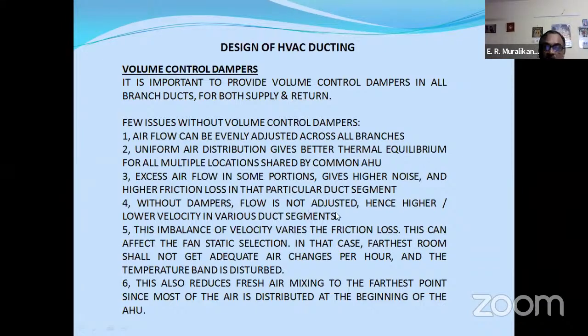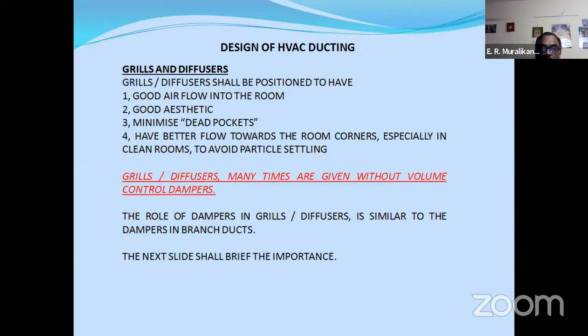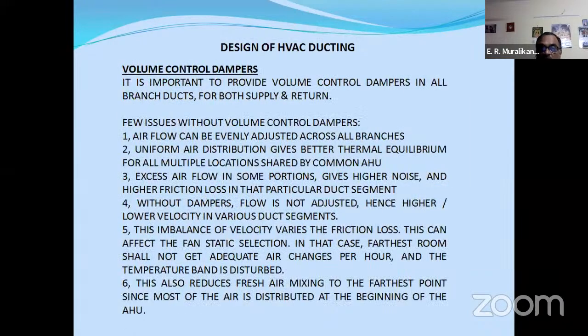Without dampers, flow is not adjusted, hence velocity is higher or lower in various duct segments. This imbalance of velocity varies the friction loss. This can affect the static pressure selection also. In that case, the farthest room shall not get adequate air changes per hour and the temperature band is disturbed. This also reduces fresh air mixing at the farthest point since most of the air is distributed at the beginning of the AHU. What I mean to say is, if one AHU is distributed into multiple rooms and there is no volume control damper, the first room will get good flow and the farthest room will not get adequate flow.